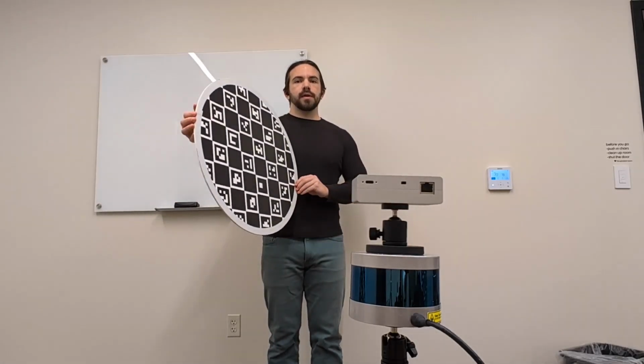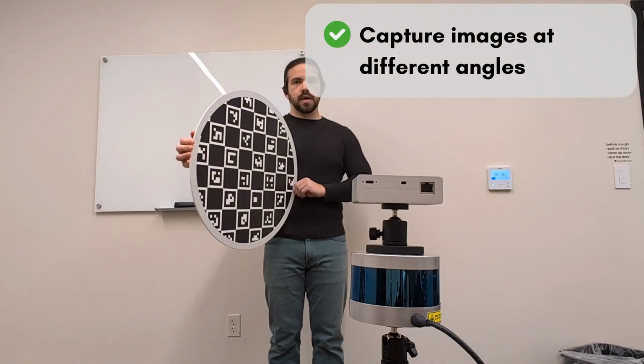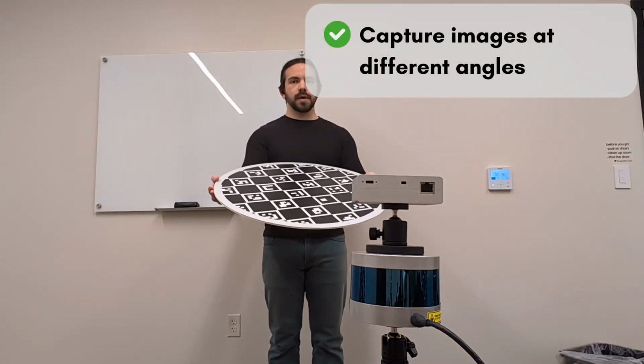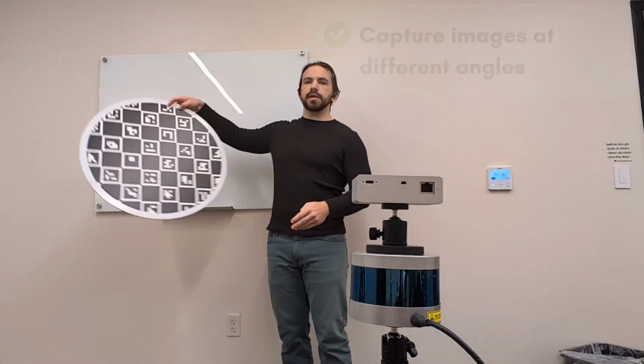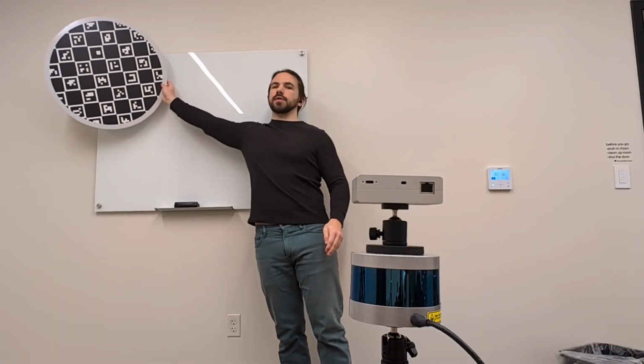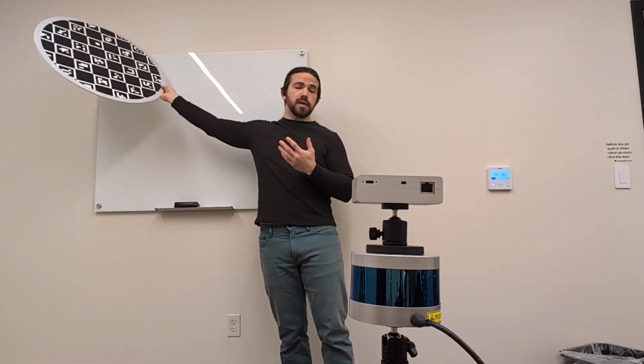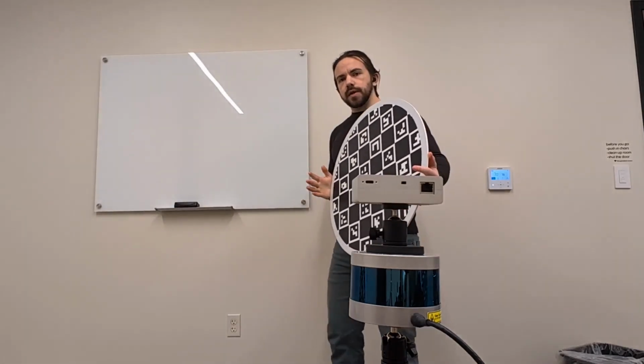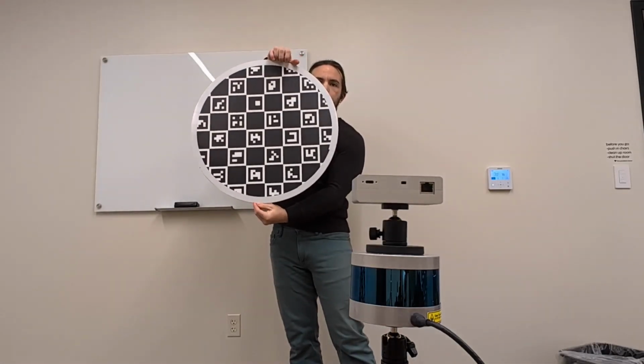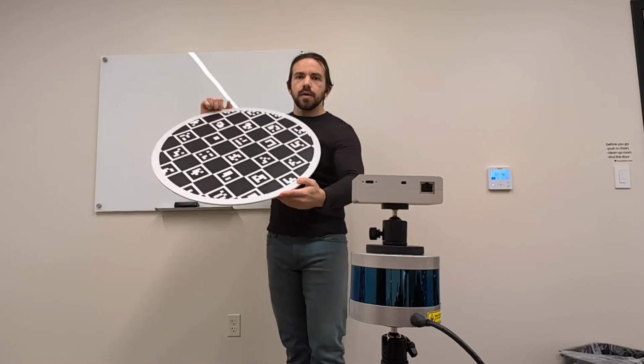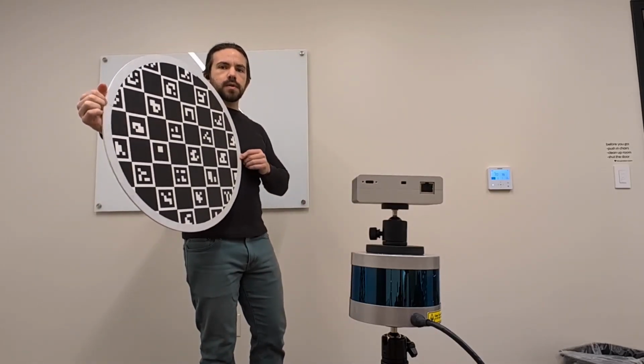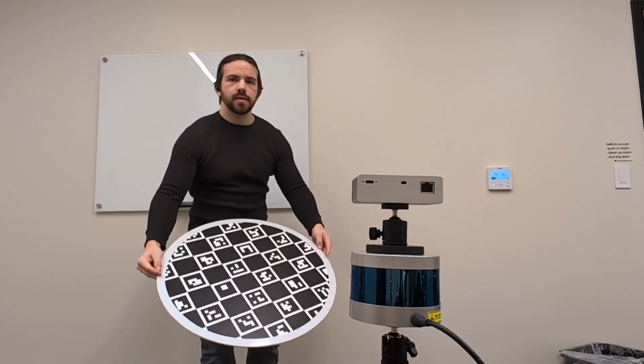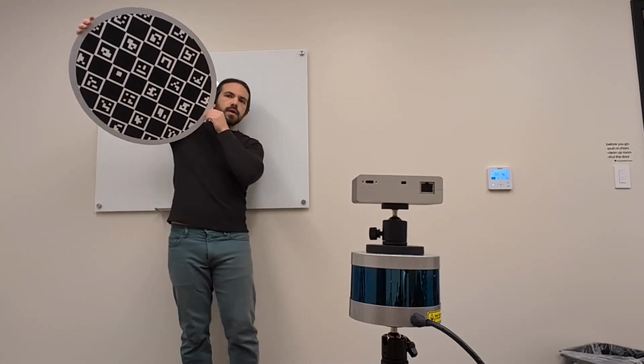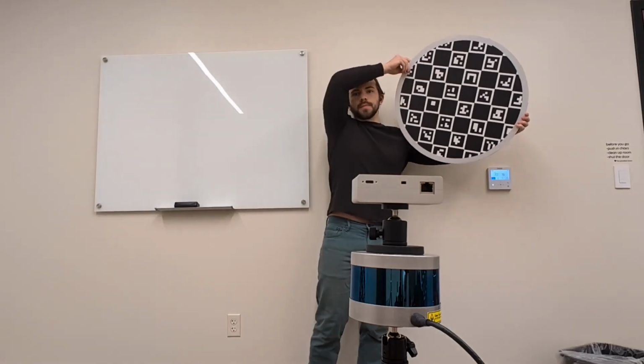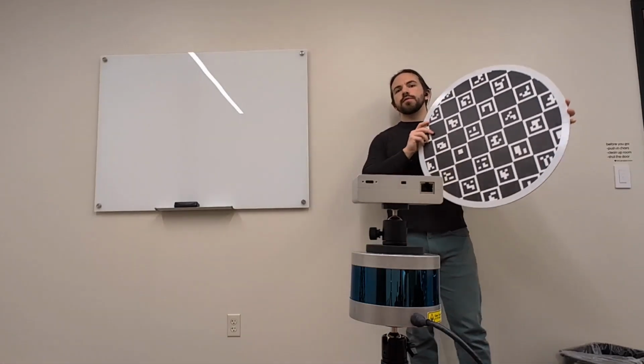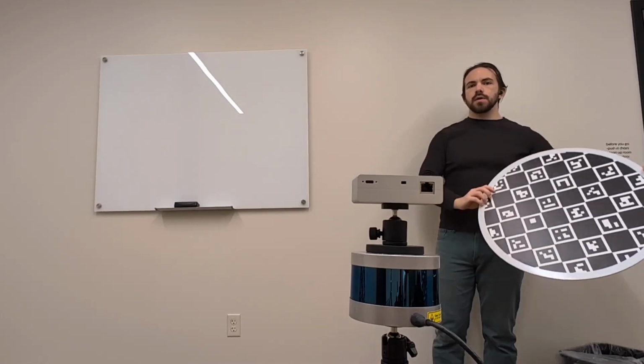So what we really want to do is hit those angles. Our detectors are very good. Don't worry about detections getting lost unless your detector is very far out, in which case the resolution of the image is just going to drop. Not our fault. Make sure to get these angles, rotate the board in all three roll, pitch, and yaw axes. And then, dip down. Go back and forth with this. Go far and close. And just do this until you get the full field of view of the camera.